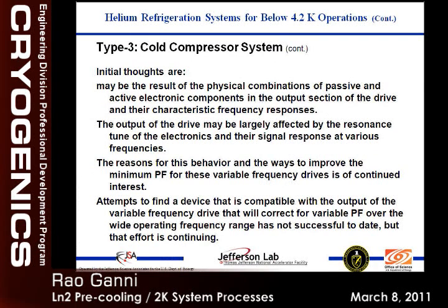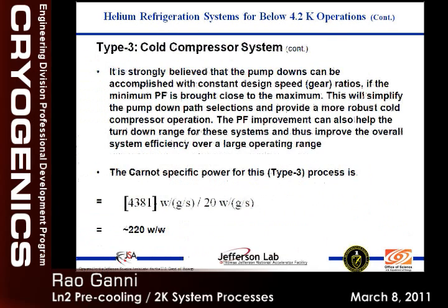Then we were looking at how to correct this power factor. We could not come up with one at that time. I don't know whether Fabio is still looking or gave up, but we could not figure out how to correct this power factor without interfering with the electronics they supply. So basically, we are living with that path. We figured out where the gear ratios are such that no more than one will hit a low power factor at a given time.